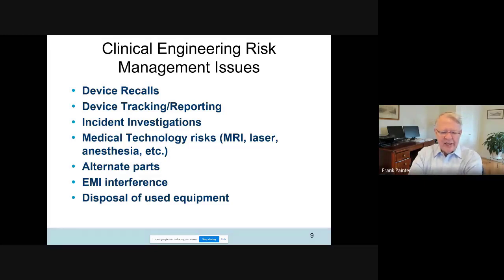We keep track, we have an inventory of every medical device in the organization, and we keep track and we report which devices are being maintained, which devices maintenance is overdue, which devices have failed more often, which devices are being reported as not working, but the technicians can't find anything wrong, so it may be a user problem. So we track the equipment and we report to the safety committee. We look at medical device accidents or incidents, and we investigate them.